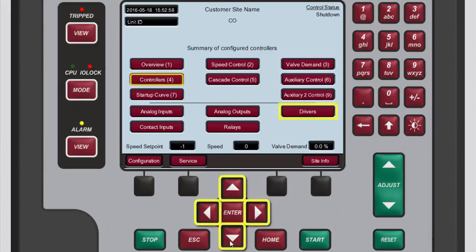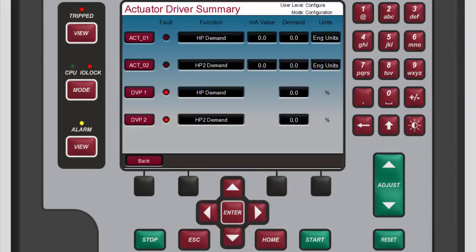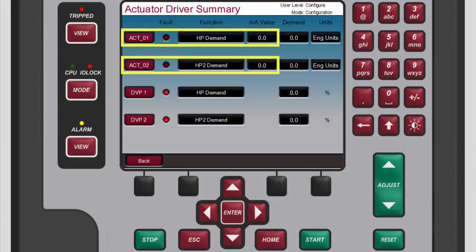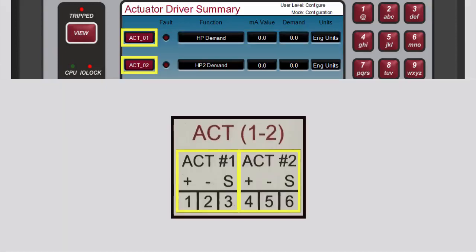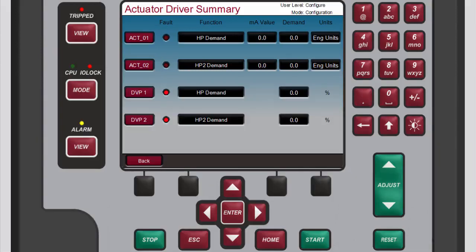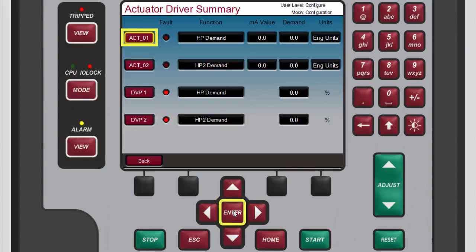To access the actuator driver summary screen from the home screen, use the navigation cross keys to select drivers, then press enter. On the actuator driver summary screen that opens, both channels are displayed along with their fault status, function, milliamp value, demand, and units. Remember, each of these channels corresponds to the similarly numbered input terminals on the back of the 505. To select an actuator channel to configure, use the navigation cross keys to highlight the desired channel — for this demonstration we'll choose actuator 1 — then press enter.